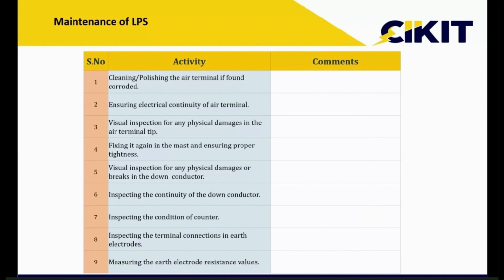And one more thing is we need to ensure whether the earthing is in good condition or not, because we are receiving this energy and we are diverting it to the ground. So if the earthing is proper, then most of the damages can be avoided. The earthing plays an important role in ensuring the safety of people and in discharging this current to the ground without much increase in the ground potential rise. So these are the points which we have to ensure while performing the maintenance of the lightning protection system.